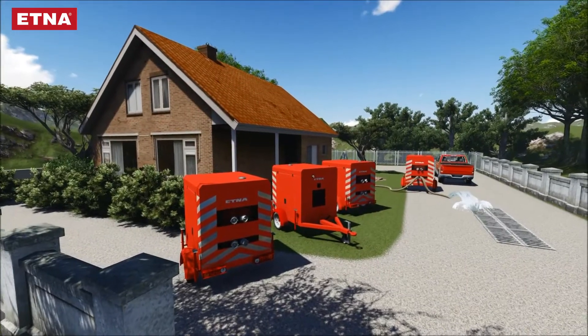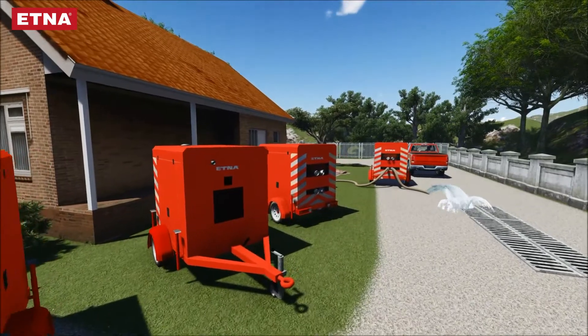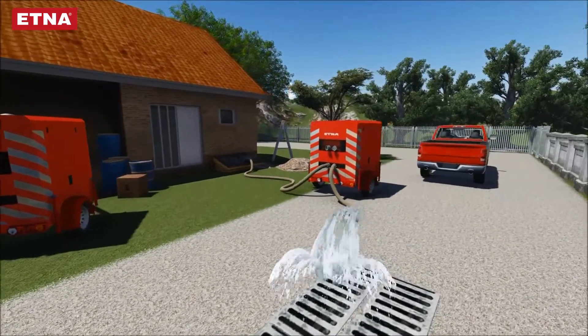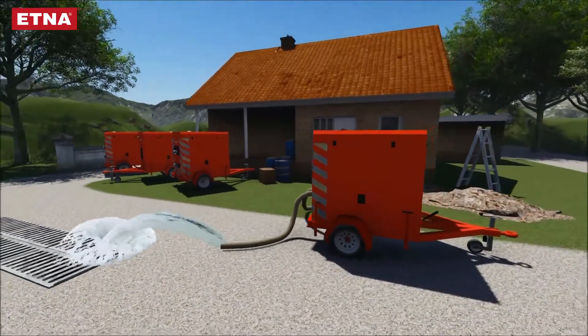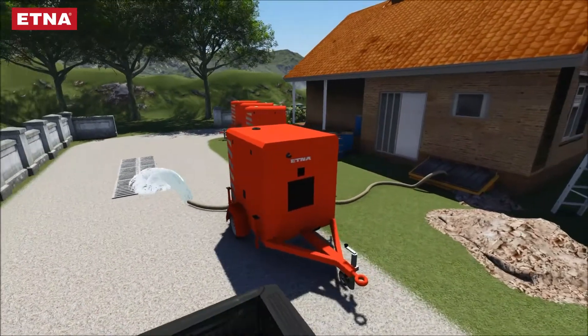If the fire is to be intervened, it should either go with a water tanker or be moved to a water source — well, pool, hydrant, etc. If the flood drainage function is to be used, it should be moved close to the flooded area, the suction hoses should be left in the water, and the exhaust vacuum system should be activated to fill the pump suction line with water.